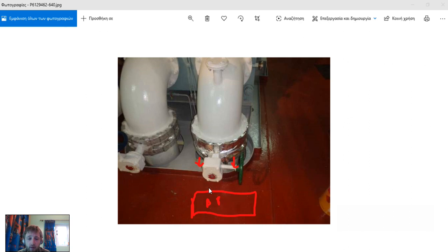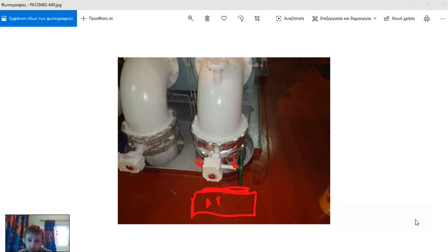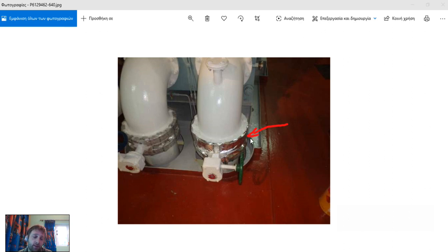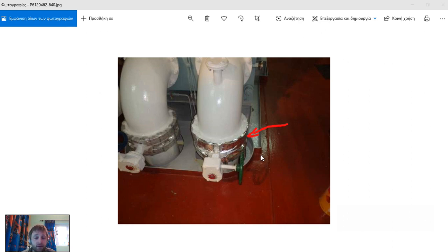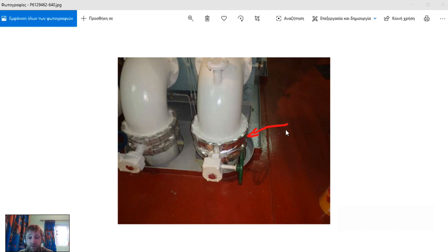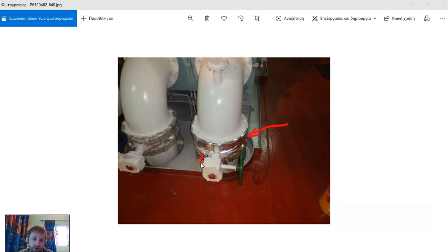All the rust will be accumulated on the body of the pump. That is the reason I do not like such protection from splash tape, because it's not visible to the eyes. This is the condition of the flanges. These sacrifice flanges have a maximum lifetime of about six months.